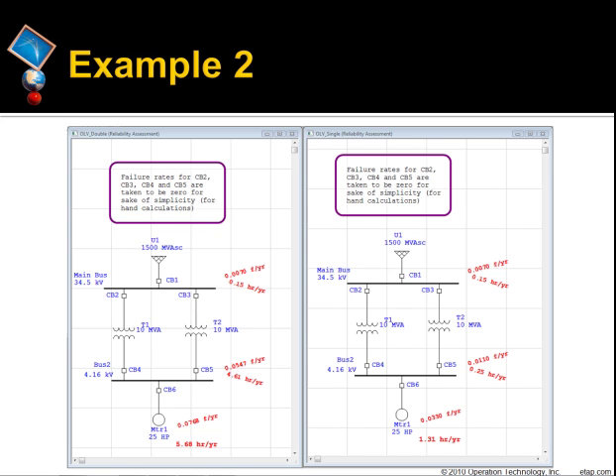Example 2. This example is for a parallel system. We will now compare the results between single contingency and double contingency cases. For simplicity, the failure rates for breakers connecting the transformers to the buses are equal to zero. We notice that for double contingency analysis, the indices at main bus are the same but are a lot higher for bus 2. This is due to the consideration of both transformer T1 and T2 failing at the same time. I will go to ETAP and open this example to show you the calculations.